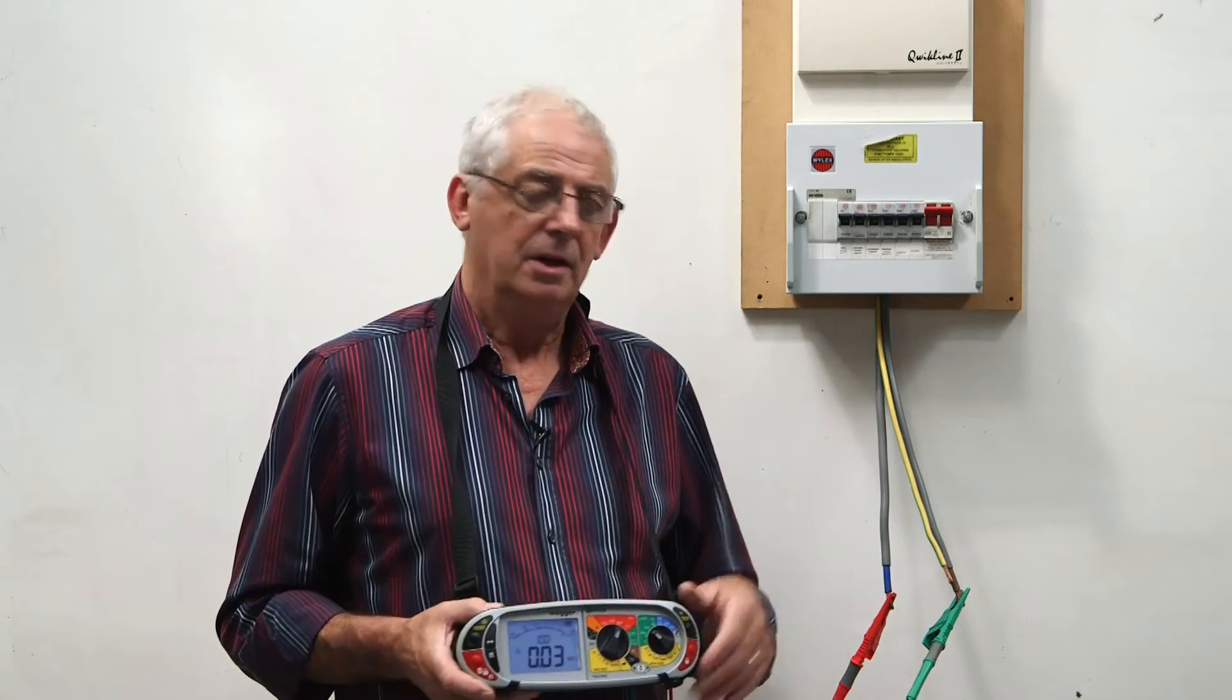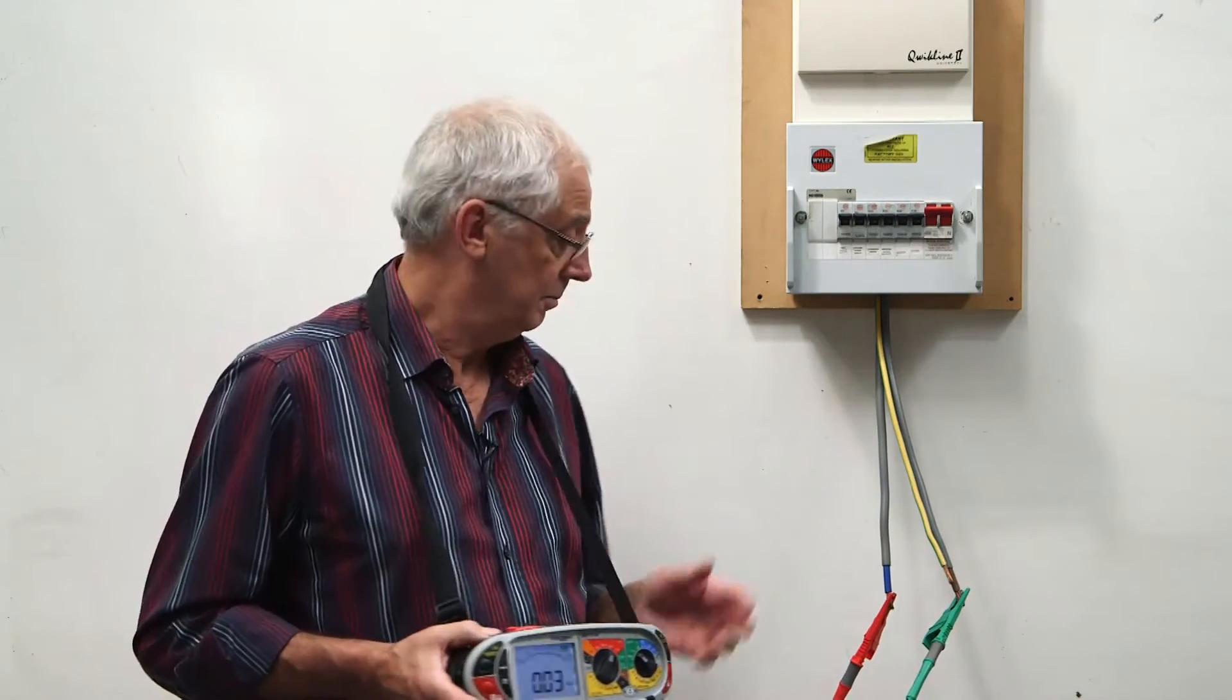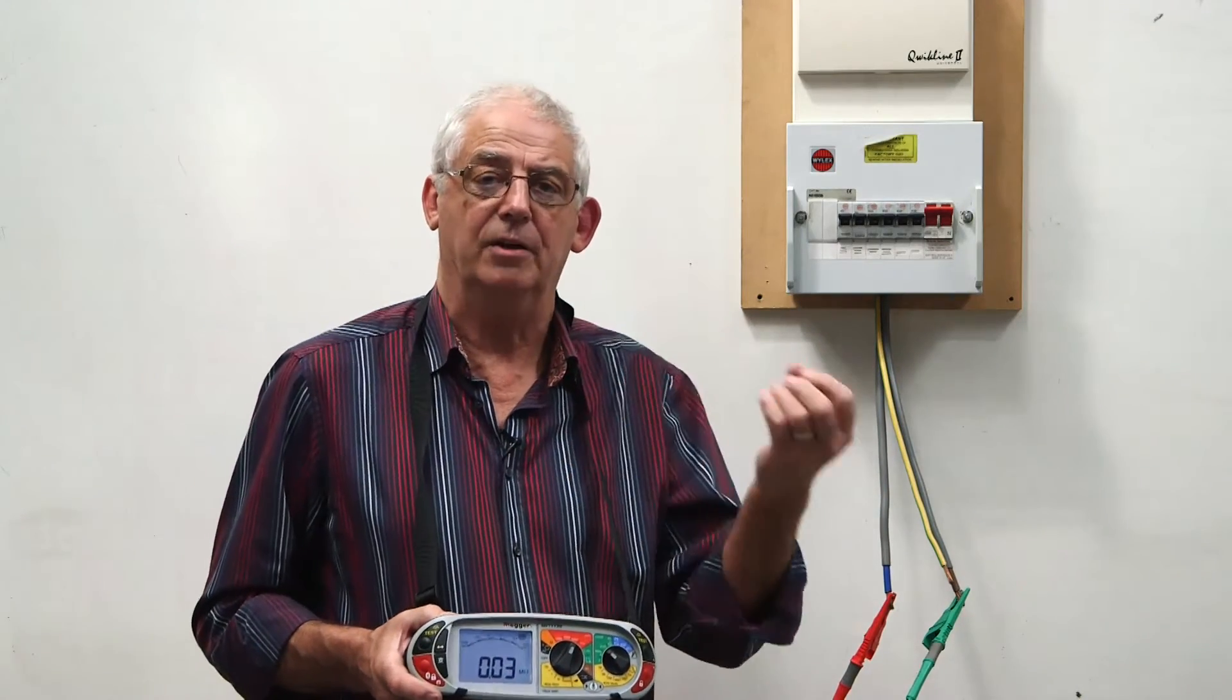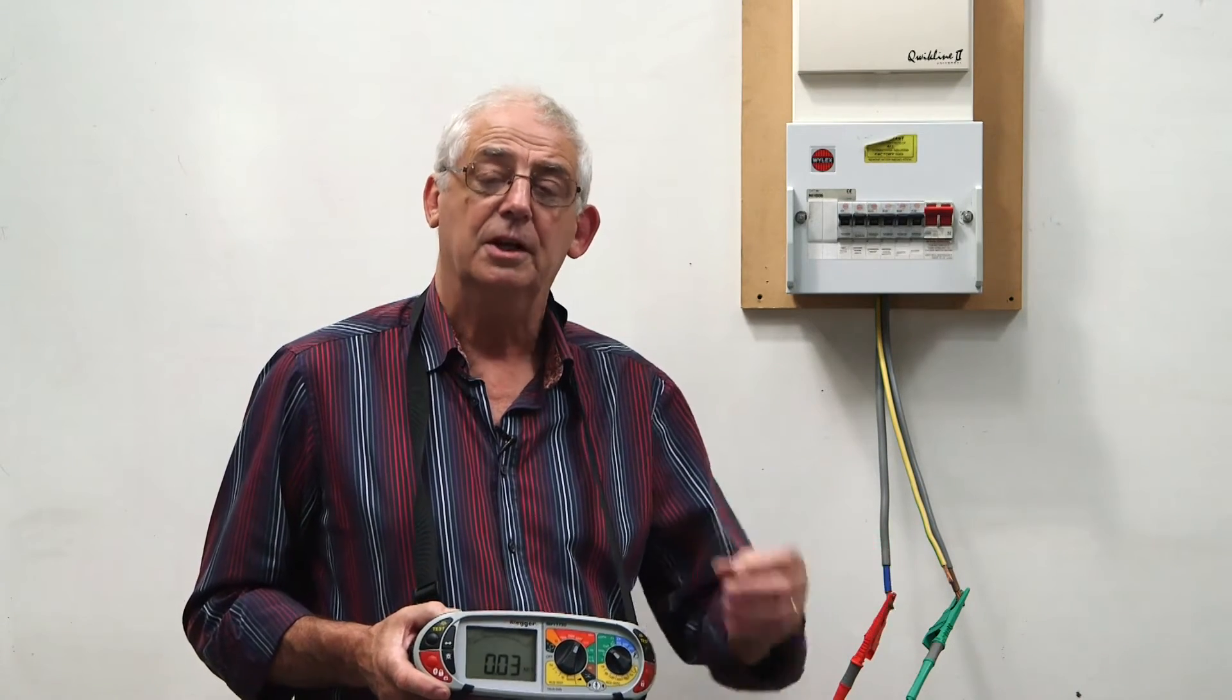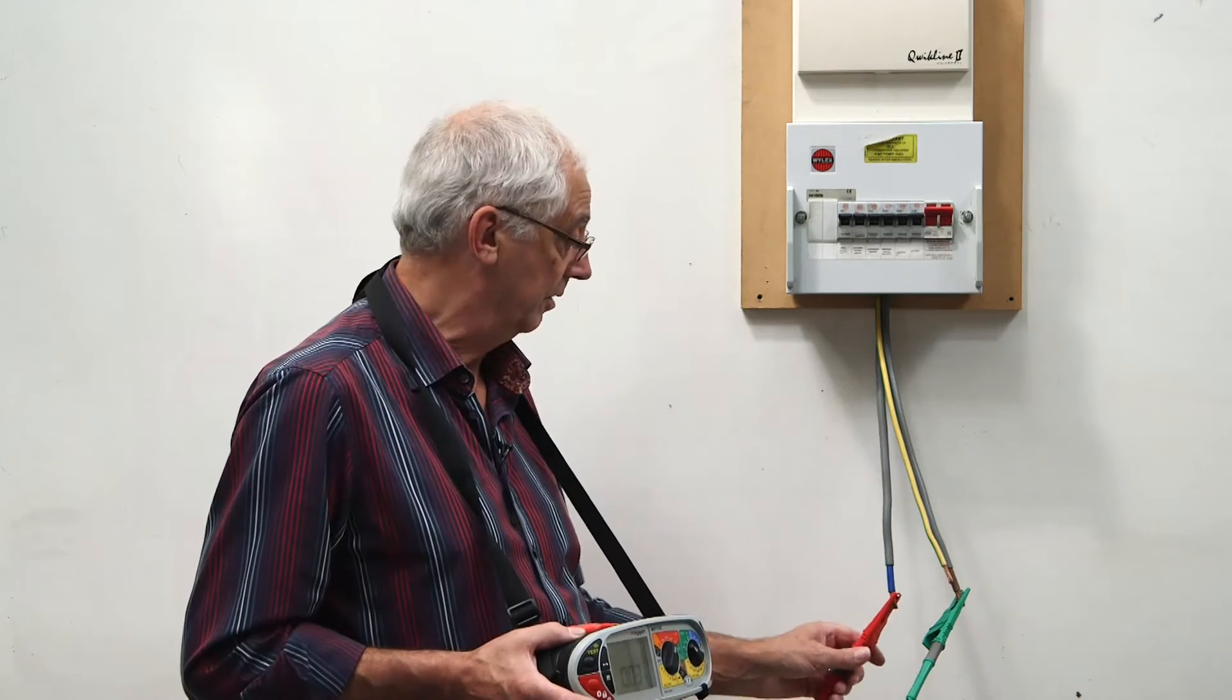Okay, I know there's a fault between live conductors, but there's no reason why I shouldn't carry on and do the rest of the insulation resistance test first before I start looking to see where the fault may lay.